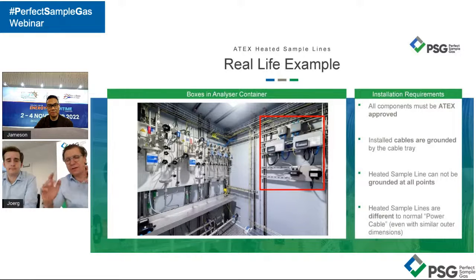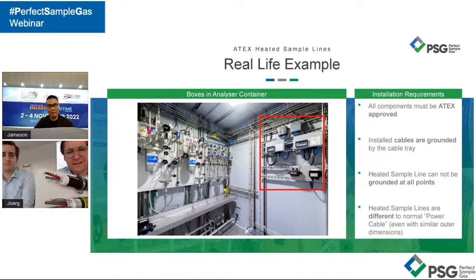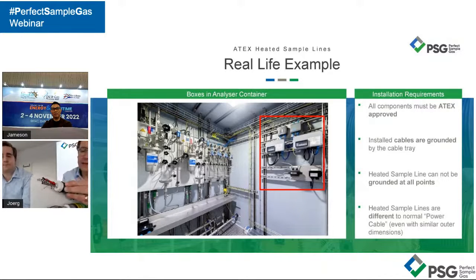All normal power cables are grounded here in the cable tray. There's a big difference when we discuss this, because people say standard electrical cables aren't conductive. The point is the difference in the architecture. If you look at a standard cable, underneath you have copper and insulation material, so a potential can build up due to wind, due to cleaning, due to someone passing by. That's a big difference between a heated sample line and a standard electrical cable, even if the dimension is the same.